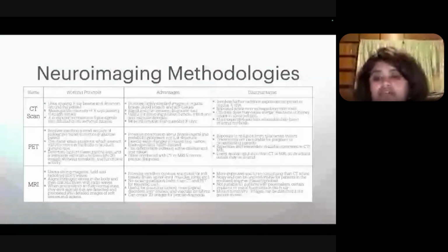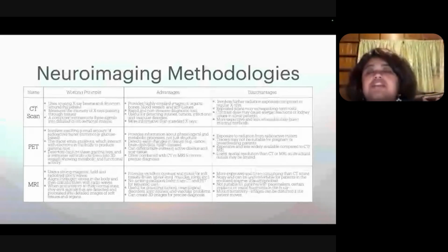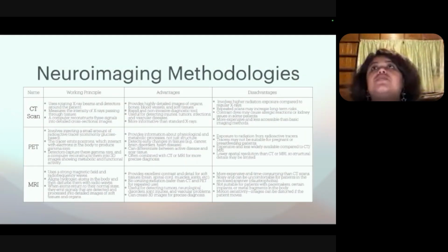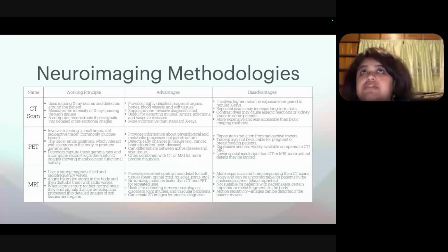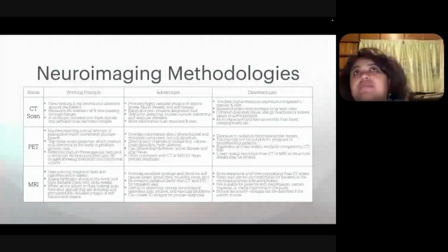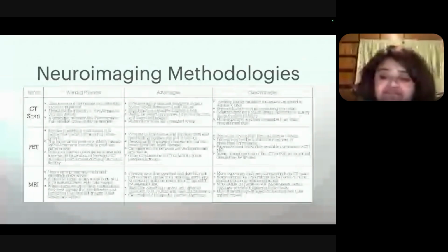And there is also a problem that when the patients are inside, now the patients who have neurological problems oftentimes show motor sensitivity. They will have repeated movements. It can be very random eye movements. Sometimes if the patients come with Parkinson's, they will also have a little bit of movement of the jaw, lips, and the head. So these motion sensitivities are there. Initially it was a big problem, but now we have software where we can code and actually remove these artifacts, these motion problems.